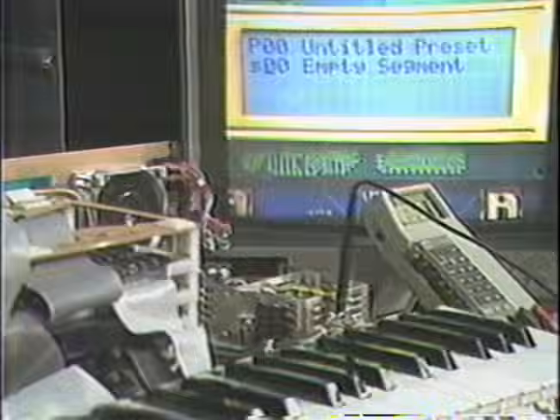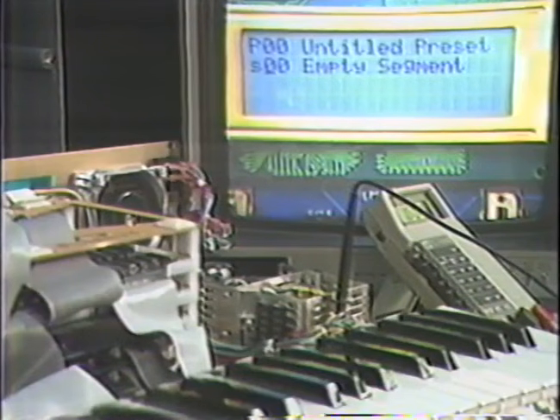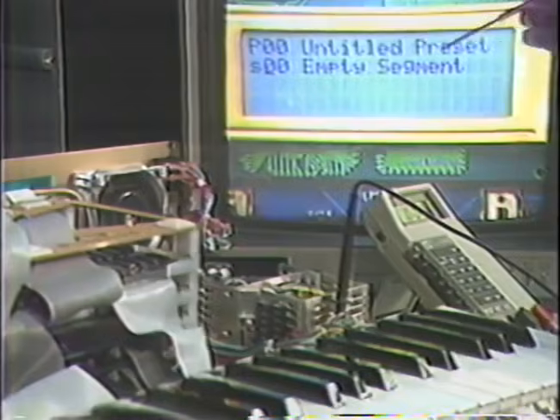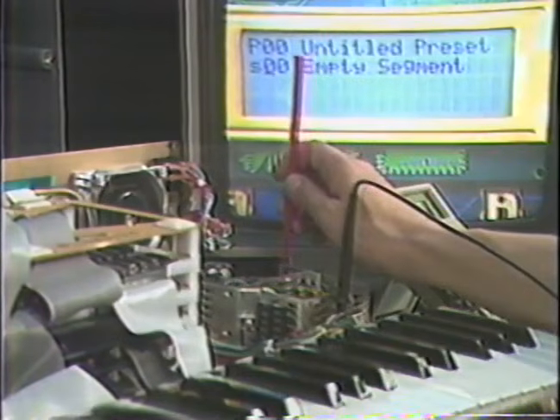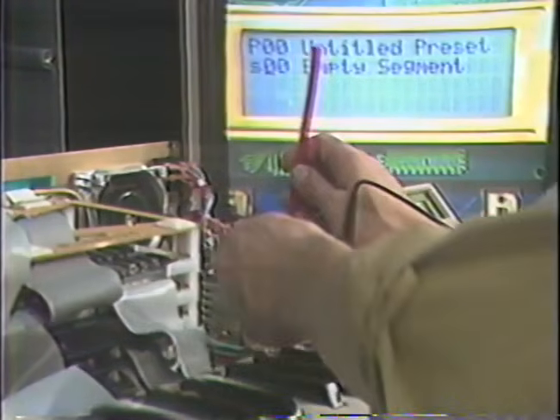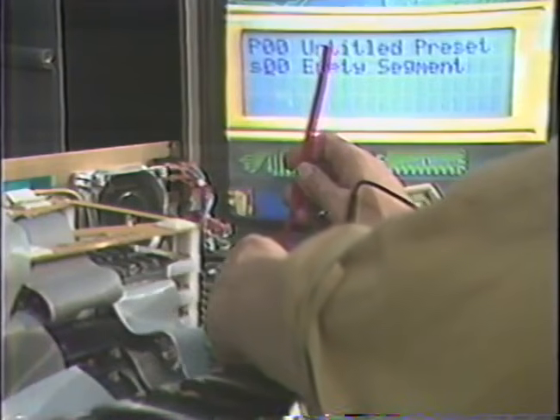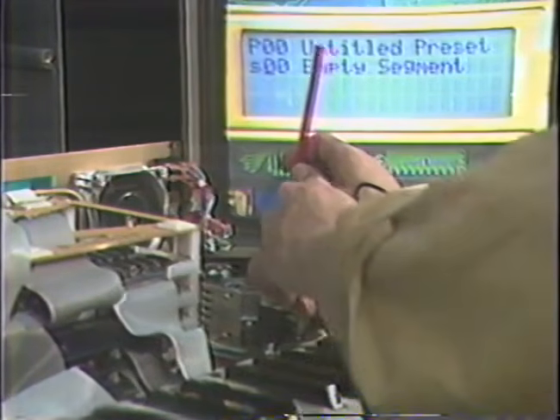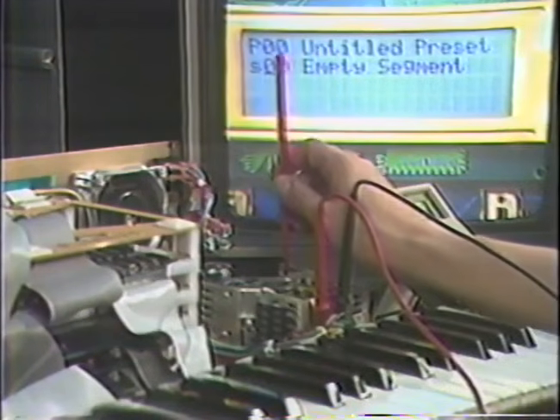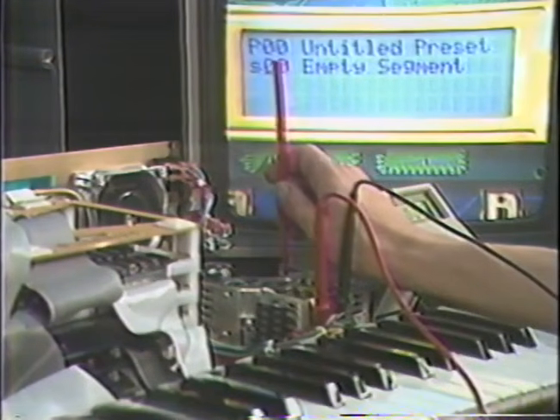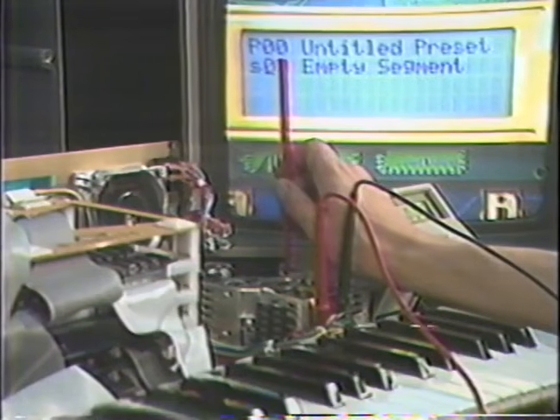Before performing any of the trims to the E3, be sure to let it warm up for at least 1 hour. This will ensure that the E3's condition is typical of its actual use and will allow the temperature of the components to stabilize. The first trim should be the plus 5 volt line on the power supply. This can be accomplished while the E3 is open, in the service position, and on the technician's bench. Use a digital multimeter only, as accuracy down to 1/100th of a volt is necessary. Measurements of 5.02 are taken at the Molex connector on the front of the power supply.